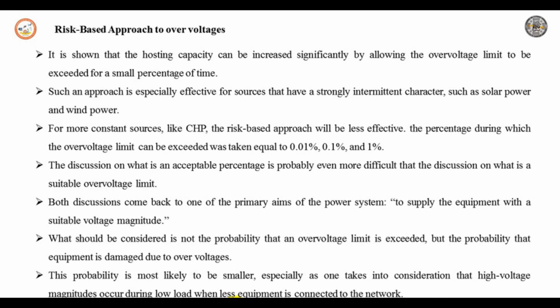The great unknown in the discussion of permissible voltage is the immunity of equipment to over voltage. Although the value of 110% of nominal is often mentioned, there are a number of studies confirming that equipment starts to experience damage when the voltage slightly exceeds this limit. On the other hand, customers complaining about damage to equipment often turn out to be experiencing damage not due to this high voltage magnitude. The most sensitive piece of equipment appears to be the incandescent lamp. Modern types of lighting are less sensitive to over voltage.